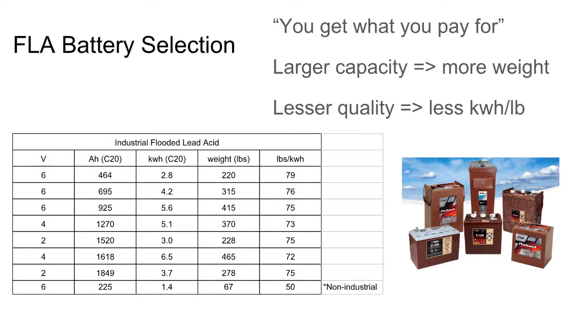And unlike in a solar array where mismatch causes one circuit to work less than another, but it's kind of okay, in a battery inverter system, mismatch between the circuits causes the whole battery system to degrade faster. And this is the $20,000 component. So that's the one component where you don't want that degradation to occur.